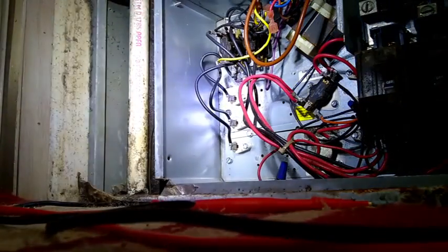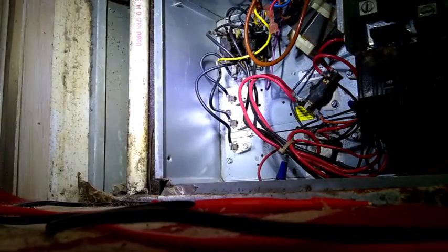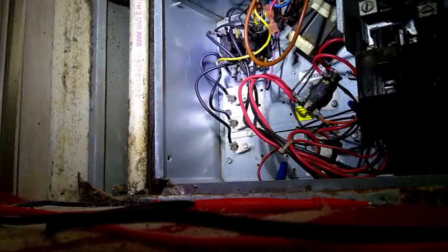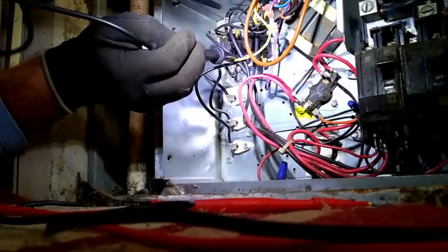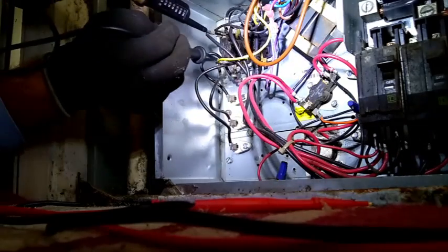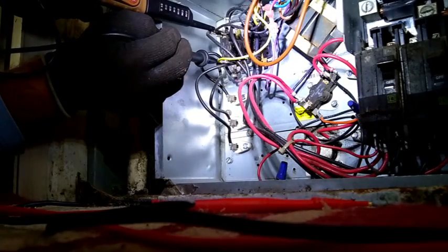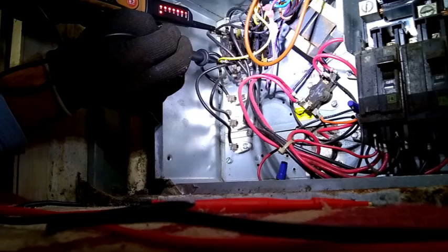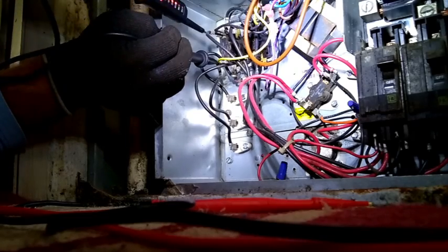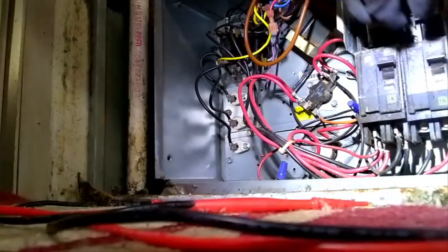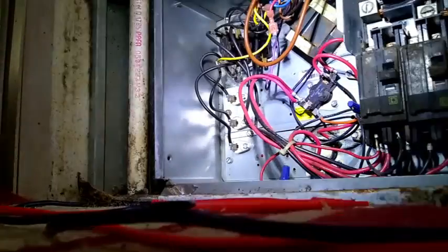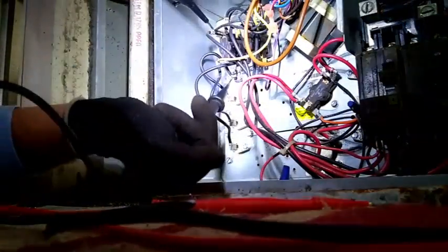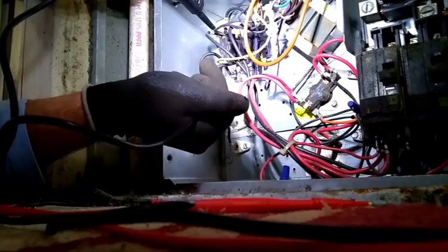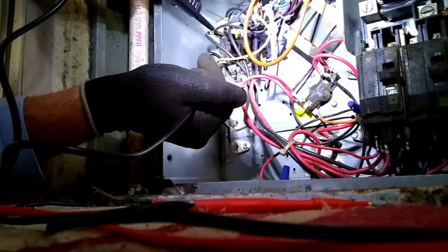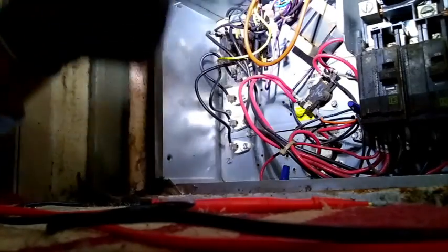That's what I'm confirming - I'm just making sure both sequencers are open. You see there's a click. I'm going over to the short stack in just a minute, and I'm going to see that it is closed and the element is actually on, and I can start to see it. I can actually see it through the cracks there, where you see those red wires going into the little double limit switch - you can actually see the elements glowing through the holes there.